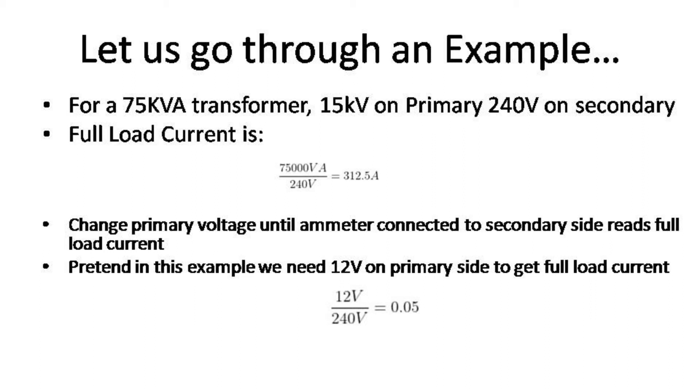Or 5% if expressed as a percentage. In fact, 5% is actually a very common impedance percentage that you will find within transformer nameplates. And that is how you measure transformer impedance.